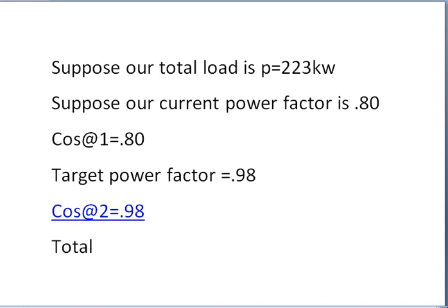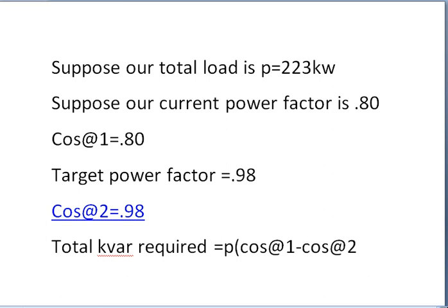Total kvar required is equal to P into cos phi 1 minus cos phi 2.